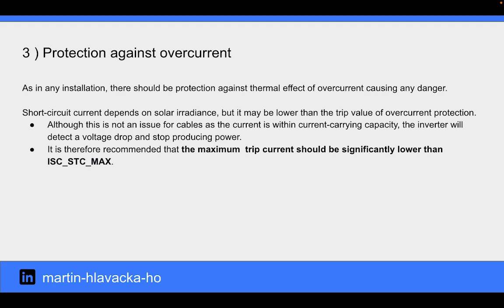As in any installation, there should be protection against thermal effect of overcurrent causing any danger. Short circuit current depends on solar irradiance, but it may be lower than the trip value of overcurrent protection. Although this is not an issue for cables as the current is within current carrying capacity, the inverter will detect a voltage drop and stop producing power. It is therefore recommended that the maximum trip current should be significantly lower than the maximum short circuit current.